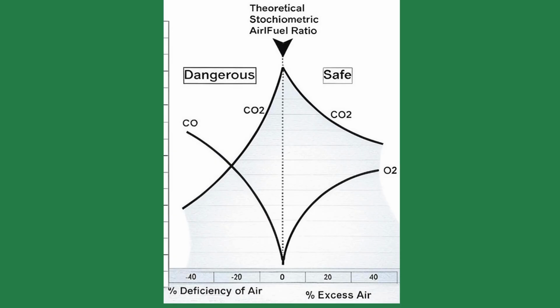Years ago, we measured only CO2, better than eyeballing the flame, but still a problem. Look at the stoichiometric chart. CO2 shows up on both sides of perfect combustion. You could have 12% CO2 and still be producing CO, or just a bunch of excess oxygen. You have no idea which. Once analyzers started showing both O2 and CO, we knew which side of the line we were on.